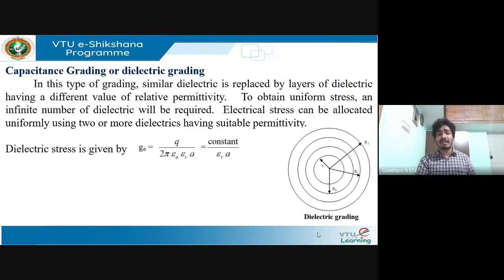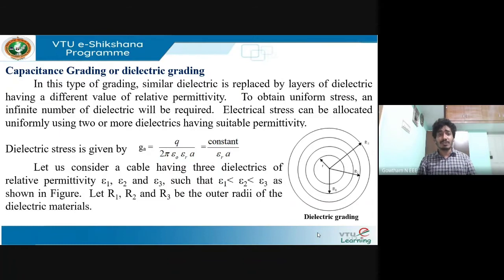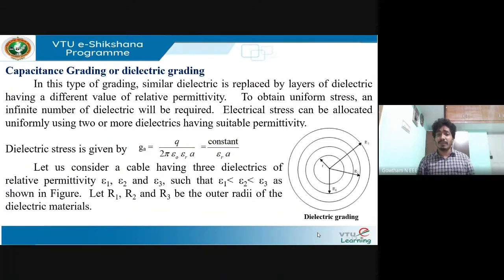The expression for dielectric stress is g_a = q / (2π ε₀ εᵣ a), where q/(2π ε₀) is constant and εᵣ and a are variables. To complete capacitance grading, three dielectrics are considered for a cable, each with relative permittivity ε₁, ε₂, and ε₃, such that ε₁ < ε₂ < ε₃ as shown in the figure.